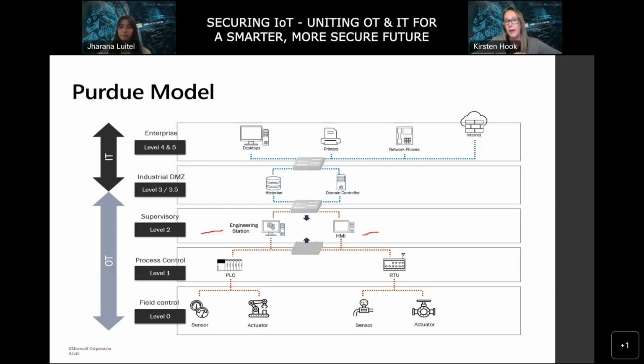And I've been in networks before where somebody used an Angry IP Scanner tool, where it's just simple ICMP. Well, guess what the PLC in this environment didn't like? It didn't like ICMP. It completely rendered the PLC inoperable. So we can't use our traditional tool sets in this area of the network.